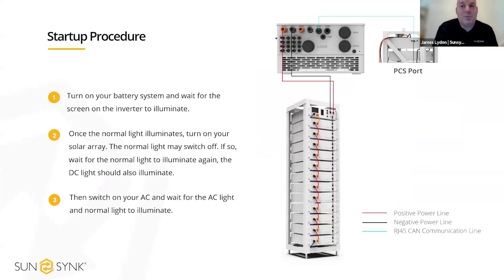So allow power to pass from the batteries to the inverter. The inverter screen will illuminate, and after a couple of minutes you'll hear the relay click, and then the normal light on the top of the inverter will illuminate. That allows you as an installer to check that the batteries are connected properly, and also that you've got good BMS comms. As they're all lithium iron phosphate batteries, we've got the positive and the negative connected to the inverter, but we've also got the BMS communications lead connected to the inverter into the PCS port.